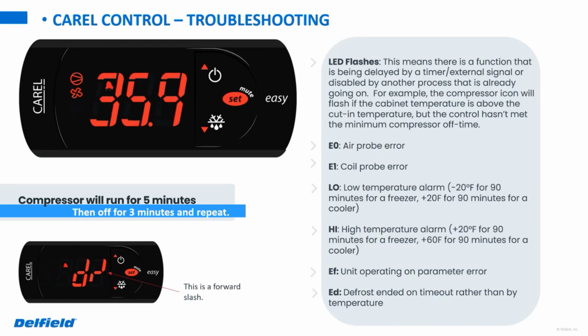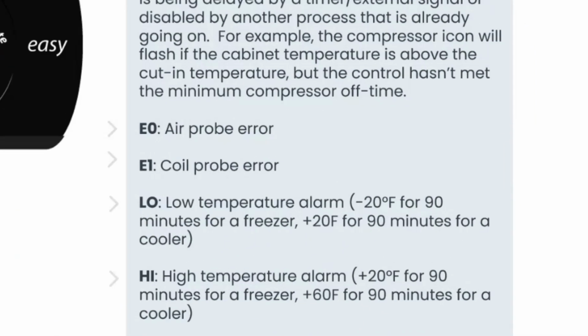As far as troubleshooting goes, you'll notice we got a handful of different errors that appear on the right-hand side there. The big ones being the E0 and the E1. Those are the different probe errors on there for the air and coil probes. Again, with those, if you have one of those errors, it doesn't really matter as far as the other probe goes because you're going to be replacing it anyway.